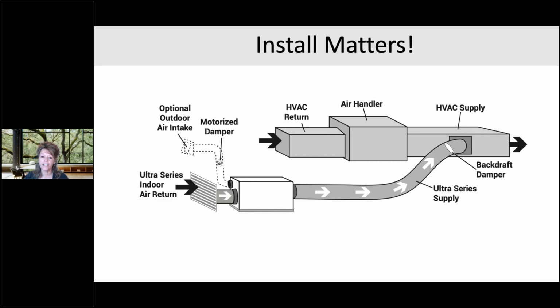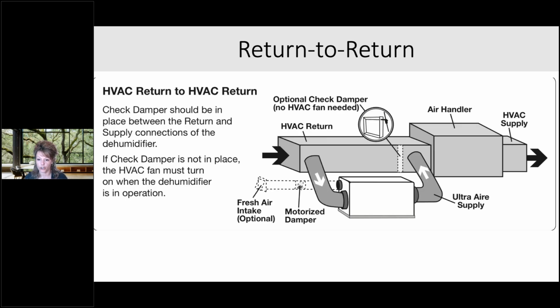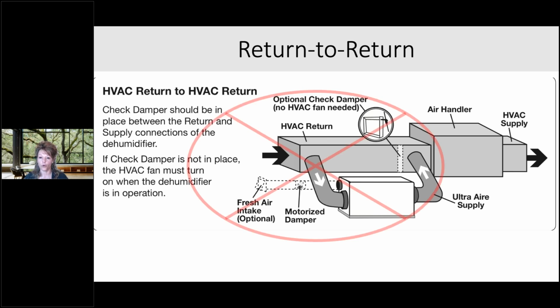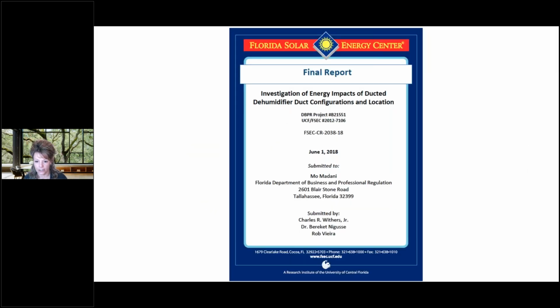If you are in Florida, this is one way per code that you can install a dehumidifier. The other way is supply to supply. You cannot pull from the HVAC return and tie into the supply of the HVAC system for the dehumidifier, and you cannot go return to return any longer in Florida. The reason for that is, this is what the return to return would look like. Florida Solar Energy released a study in June of 2018 that basically said a return-to-return install is the most ineffective and inefficient way to install a dehumidifier.